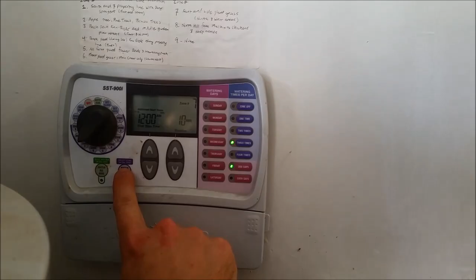You can see it's sputtering out what's left of the water in the sprinkler system, getting any excess water out of the line. Notice it only runs for a few seconds, and the air compressor is having a hard time keeping up with the air it has to push through the lines.